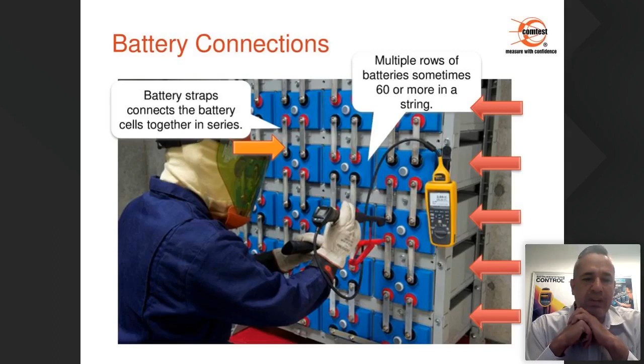So why do maintenance-free batteries need maintenance? Compared to your non-maintenance-free open-flooded battery, the valve-regulated lead-acid battery does not need to be topped up with distilled water periodically. Maintenance-free batteries need to be tested because they deteriorate in several failure modes. The first ones we're mentioning in the diagram here are corrosion, an internal short within the plates, and then sulfation. Sulfation happens on the plates when the batteries are discharging, and you can have special desulfating charges that will recondition your batteries to actually recover from this condition.